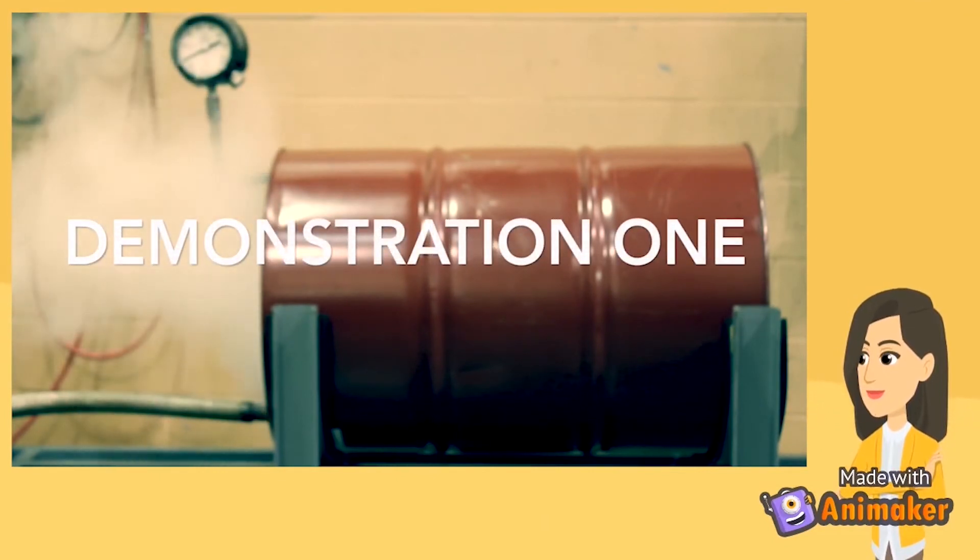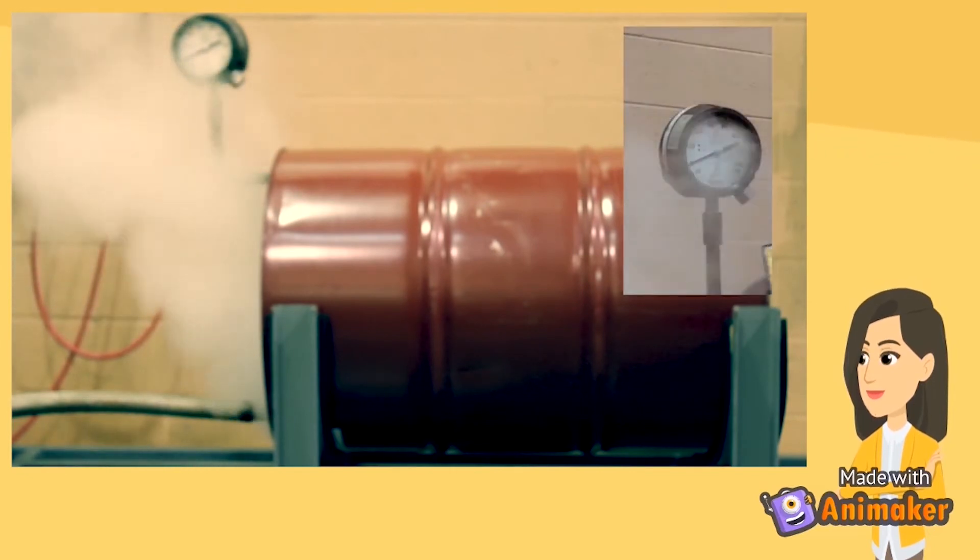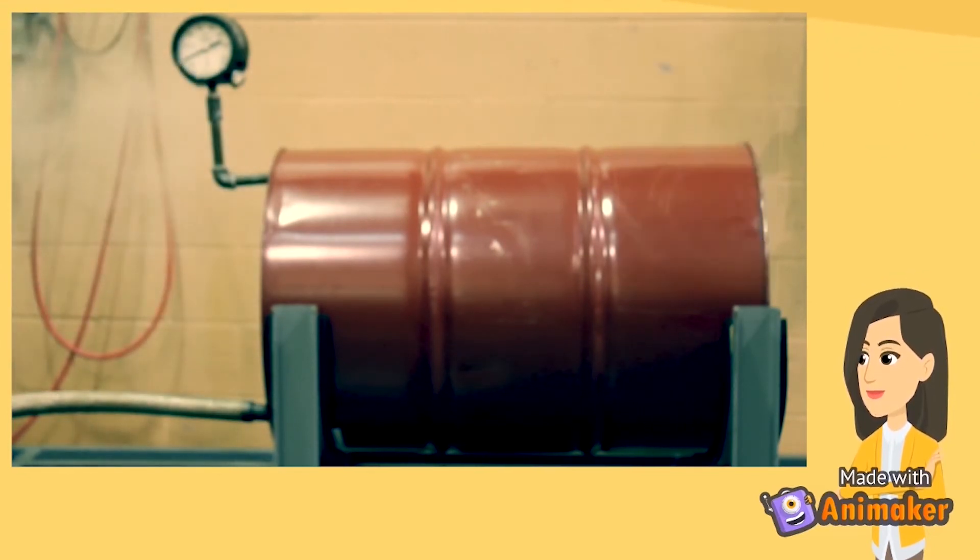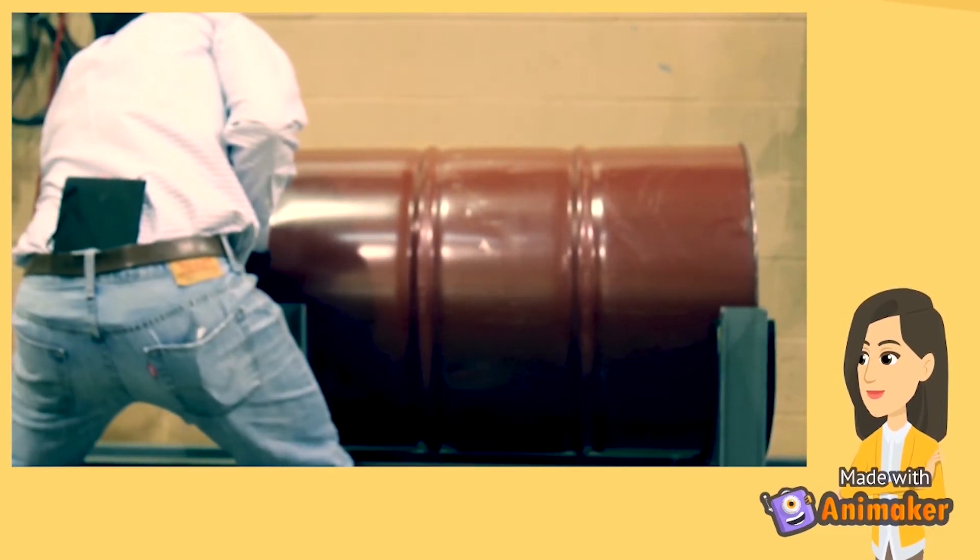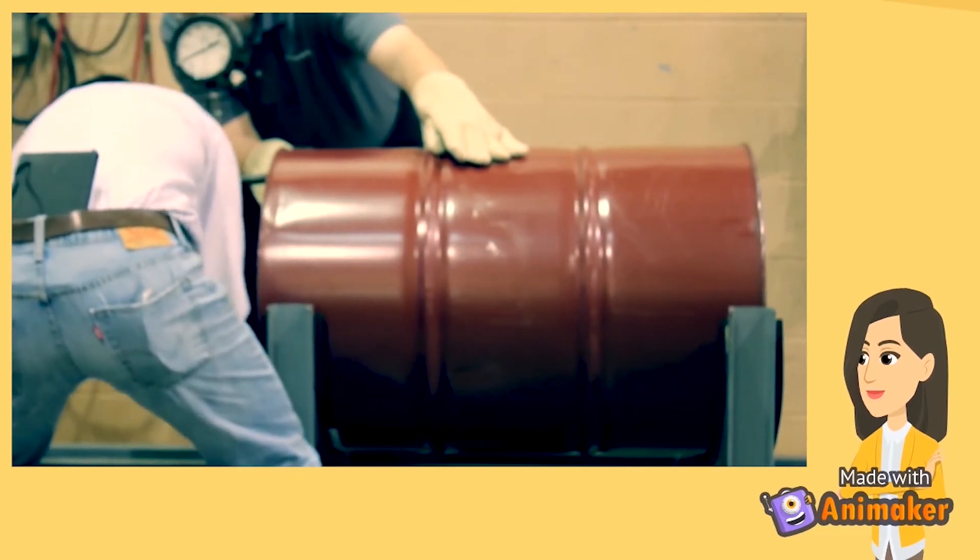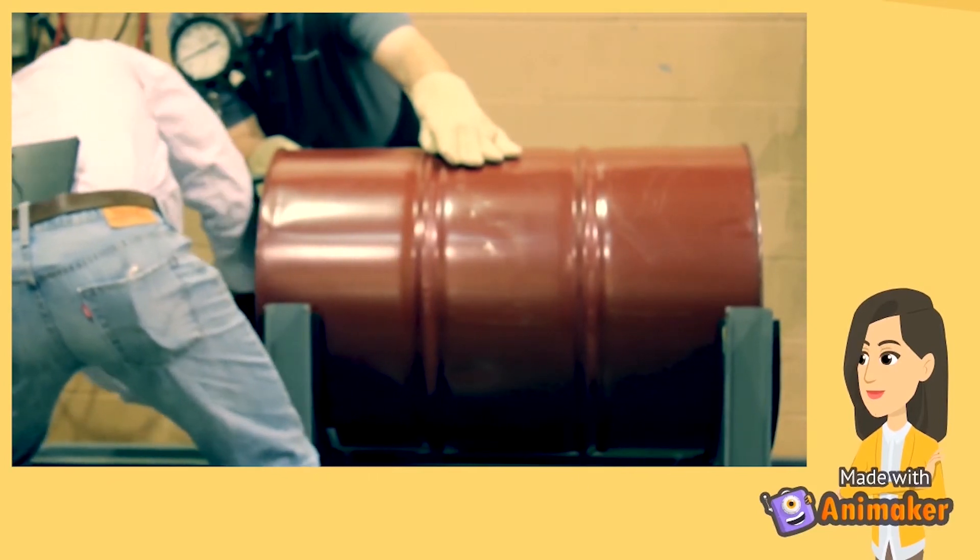The barrel begins this demonstration at 0 PSIG. The barrel in this example will be filled with steam while open to atmosphere. Once the air is purged and the barrel reaches 200 degrees Fahrenheit, we will pull the steam source and seal the barrel. Once the barrel is sealed and a condensing load is applied to the barrel, the steam inside condenses and the pressure falls. Ultimately, the pressure inside of the barrel is low enough relative to the atmospheric pressure outside that the barrel collapses.